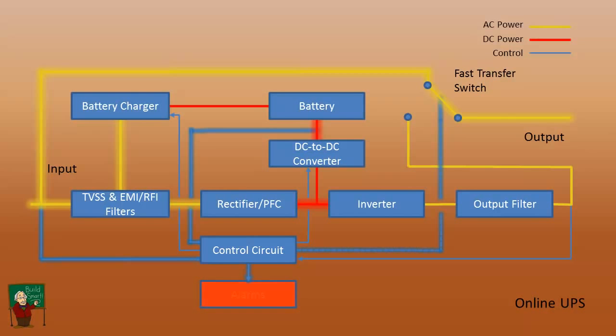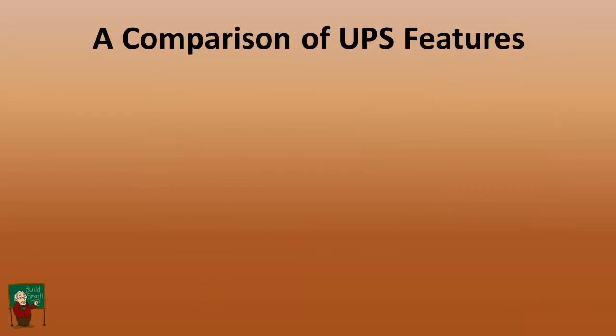So this would be in the case of something going wrong with the UPS. Now there is a very brief delay, not enough to really be a problem, but this is where there's a transfer delay on the online UPS. The line interactive has a transfer delay when there's a fault on the input power. So now we'll look at a comparison of the features of these two principal types of UPS, which would be the line interactive and the online.